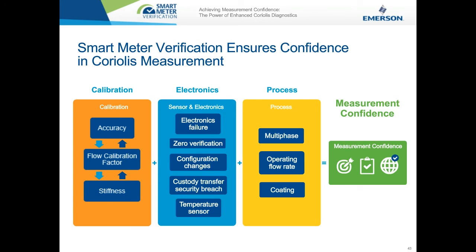Thanks, Taylor. What monitoring and diagnostics are available outside of ProLink? We use Modbus RS485 and watch a few registers for RAM, EEPROM, etc. Great question, especially when we're talking about how these diagnostics can scale with host systems. All the diagnostics that we discussed today are available through Modbus 485. Diagnostics are also available through other protocols, HART, wireless HART, for example. We can also map these to discrete outputs. So the answer is yes, they can be mapped to Modbus 485.